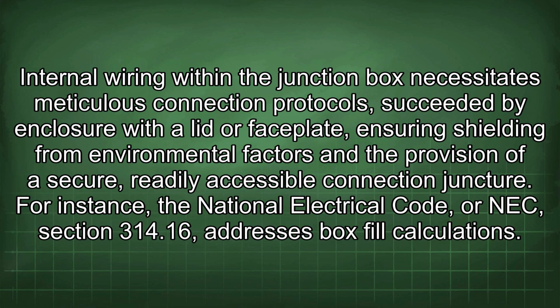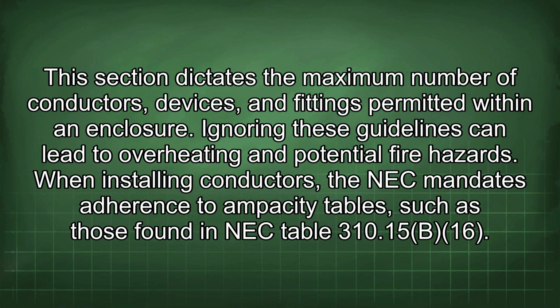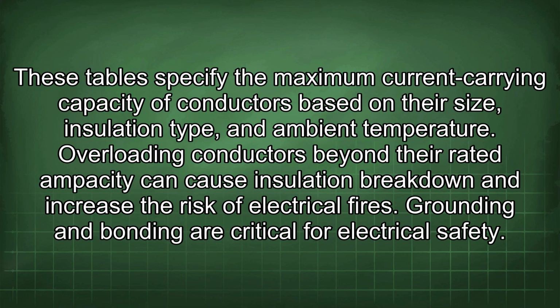For instance, the National Electrical Code, or NEC, Section 314.16, addresses box fill calculations. This section dictates the maximum number of conductors, devices, and fittings permitted within an enclosure. Ignoring these guidelines can lead to overheating and potential fire hazards. When installing conductors, the NEC mandates adherence to ampacity tables such as those found in NEC Table 310.15(B)(16). These tables specify the maximum current carrying capacity of conductors based on their size, insulation type, and ambient temperature. Overloading conductors beyond their rated ampacity can cause insulation breakdown and increase the risk of electrical fires.